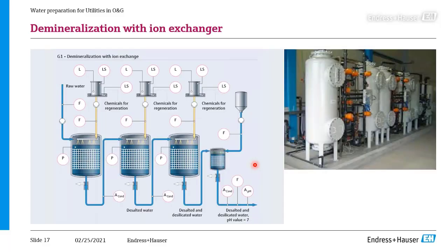And then we go to the demineralization with ion exchangers. In that case, the pre-treated raw water goes into the first, I would say, contact chamber or vessel. What happens here is that the ion exchange takes place in these columns, and from there it goes to the second one. So from there, you already have desalted water. It goes to the further treatment. Then it's desalted and desilicated water. So silicate was also removed, and from there the water is more or less ready, and it goes to the further process. And here at the end, you measure flow, conductivity, to make sure that the processes before went well, and also pH.